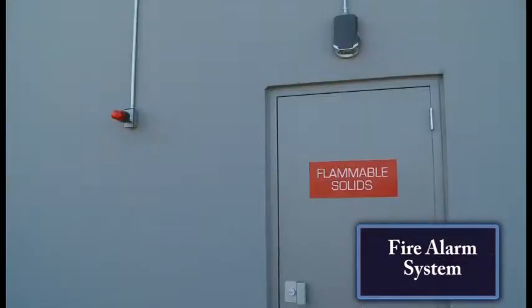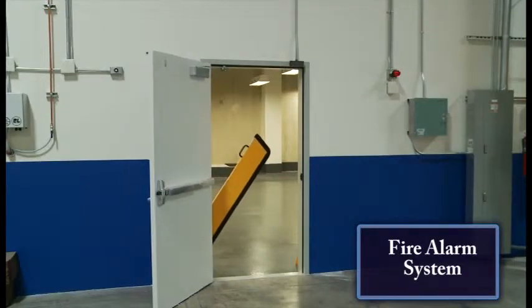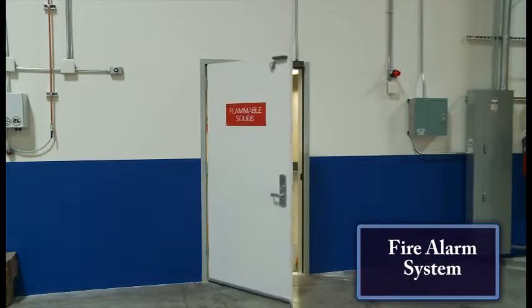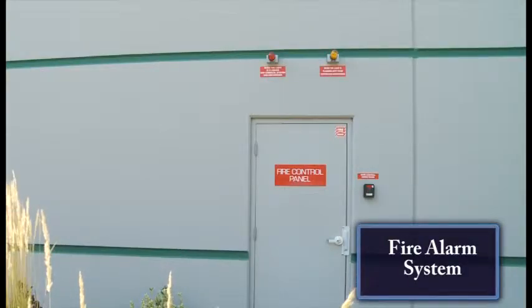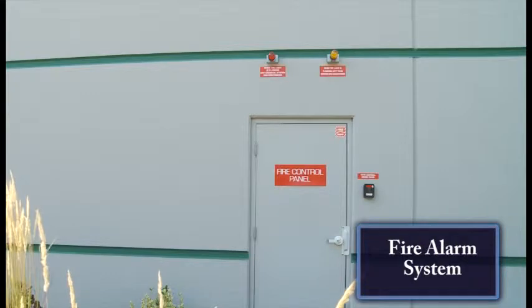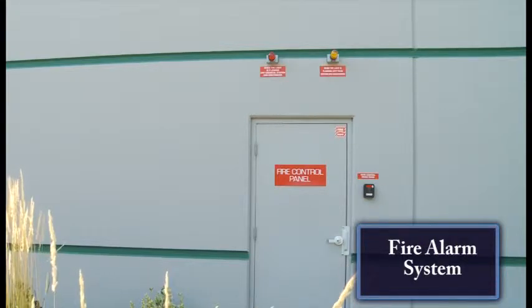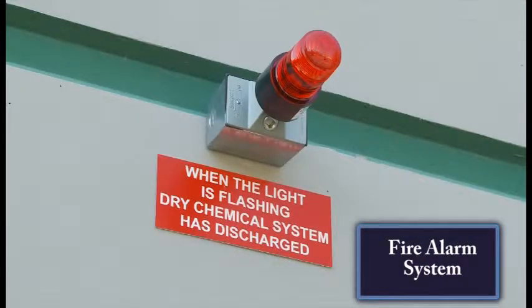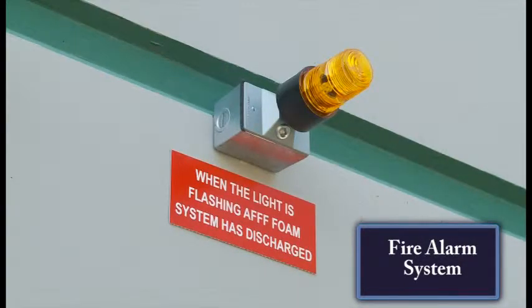Beacons are located outside of exterior and interior doors to each storage area in order to indicate which space is in alarm. 2 beacons are mounted over the fire alarm control room where first responders can easily see them on approach to the scene. A red beacon indicates the alarm is in the flammable solids water reactive storage room and the dry chemical suppression system has discharged. An amber beacon indicates the alarm is in the flammable liquids area and that the AFFF-AR foam system has been discharged.